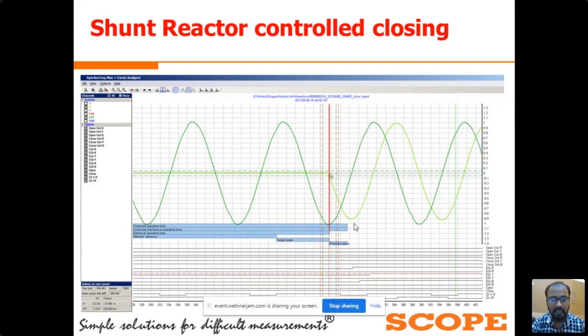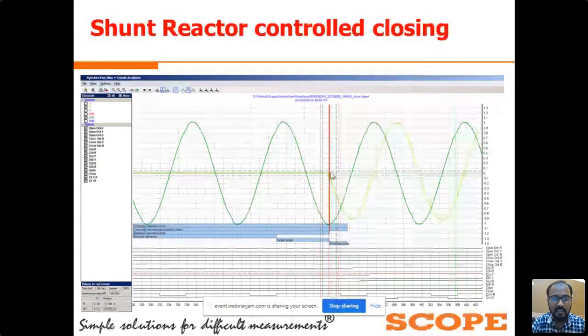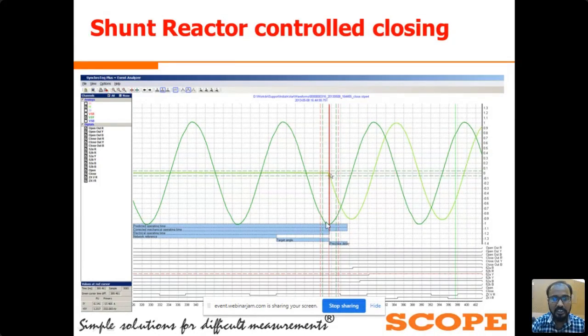So we need to calculate these things only during commissioning. But the predicted operating time, that is the breaker operating time, we can calculate through the timing test of the circuit breaker. By considering this breaker operating time and pre-arcing time, CSD will execute the command to the CB contact, and CSD tries to start this pre-arcing current at the voltage peak point. Here you can see the current started near the voltage peak, exactly at our predefined target point. We have observed there is no DC asymmetry in the system current. The current starts very gradually, and it is the same on the negative side and the positive side. So this is the waveform with the control switching.